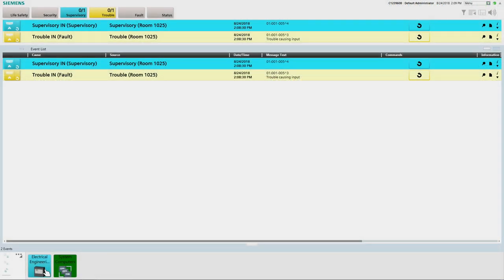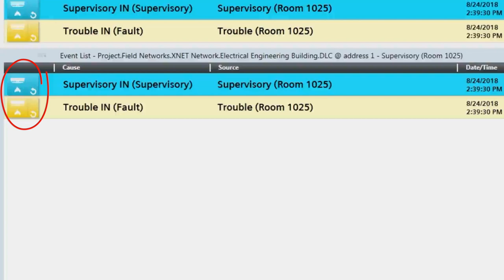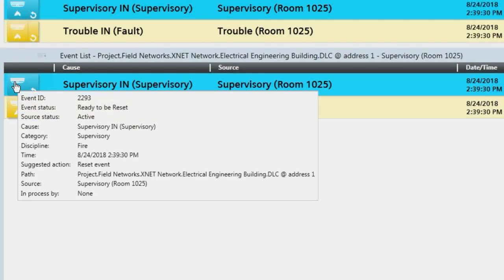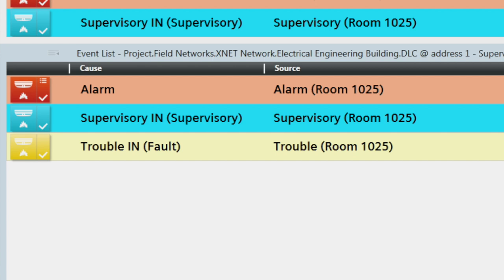Next, we have the event list, which is always located below the summary bar. The event list displays all active events on the connected panels, with a row for each event and several columns of information. Starting on the left-hand side, there is an event icon that graphically summarizes the most important information about the event. By hovering the mouse cursor over the event icon, additional information is displayed in a tooltip box. The event button will flash and the audio buzzer will sound until the event is acknowledged. The next column is the event cause column, which provides a textual description of the event cause. Then we have the source column, which indicates the physical location of the device. To the right is the date and time column, followed by the message text column, which provides more detailed information about the event cause.